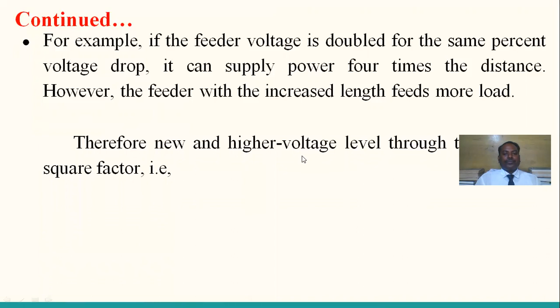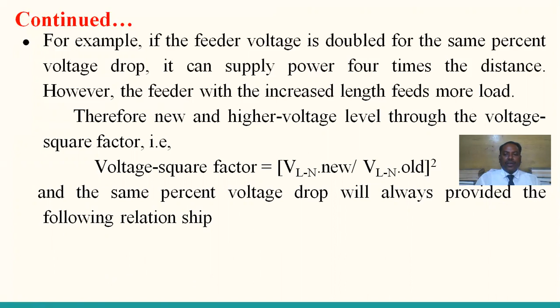Voltage square factor is equal to line to neutral voltage new, divided by line to neutral voltage existing, that is, the increased voltage by the existing voltage, whole square. And the same percent voltage drop will always provide the following relationship: distance ratio into load ratio is equal to the voltage square factor, where distance ratio is equal to new distance by old distance, and load ratio is equal to new feeder loading by old feeder loading. So as per the voltage square law, for a constant voltage drop, the feeder length and loading are direct functions of the voltage.